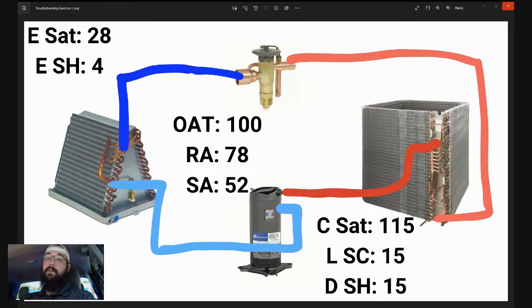Remember, we moved to high speed. We may need to go back to medium speed for humidity control. This space may not run well on high speed because of humidity. So you remember to put that fan back where we had it. Undo the things you did that were unnecessary. Put them back the way they were, unless you have a really good reason not to. And then we're also going to see that external static can come back down.